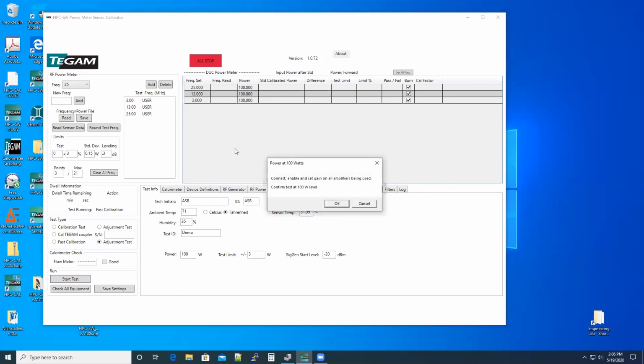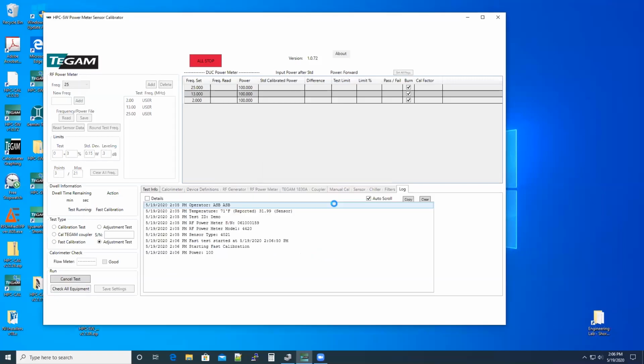So we've erased the calibration data. So I need to connect, enable, and set gain on all amplifiers being used. Well, in this sensor, I have 1 amplifier that covers the whole frequency range. But if I needed to use some of the other amplifiers, the TEGAM RF power switch 1322 selection matrix would switch us back and forth between the amplifiers under automatic control. My amplifier is on and it is set to an appropriate gain. And it says, do you want to do the test at 100 watt level? Yes, I do.